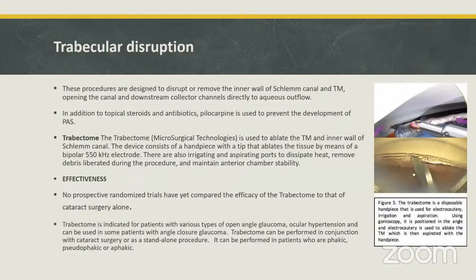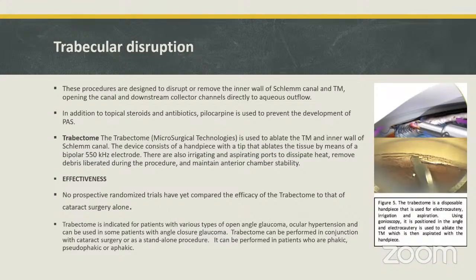The next category is methods of trabecular disruption. These procedures are designed to disrupt or remove the inner wall of Schlemm's canal and trabecular meshwork, opening the canal and downstream collector channels directly to aqueous outflow. The first device is trabectome, used to ablate the trabecular meshwork and inner wall of Schlemm's canal. It consists of a handpiece with a tip that ablates tissue by means of a bipolar 550 kHz electrode, with irrigating and aspirating ports to dissipate heat and remove debris.